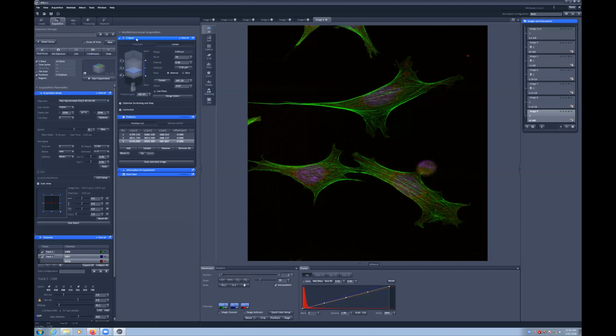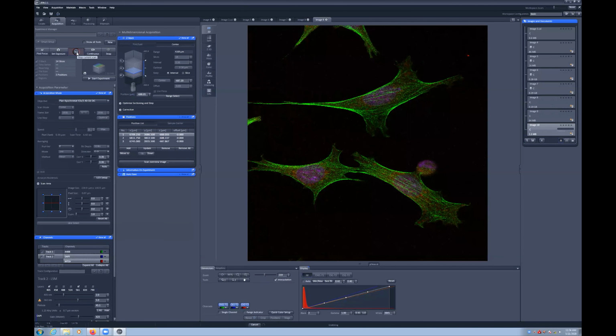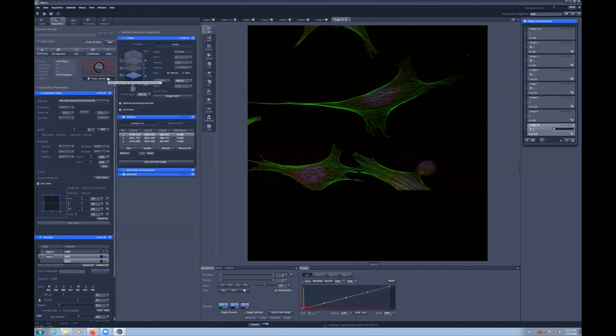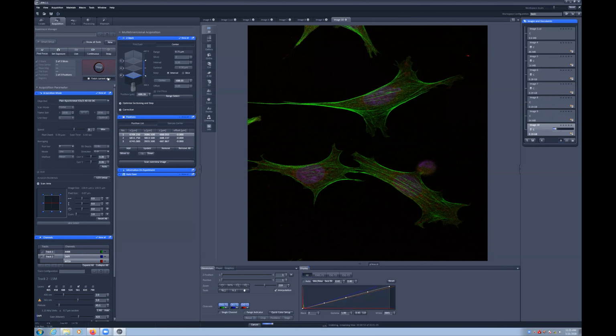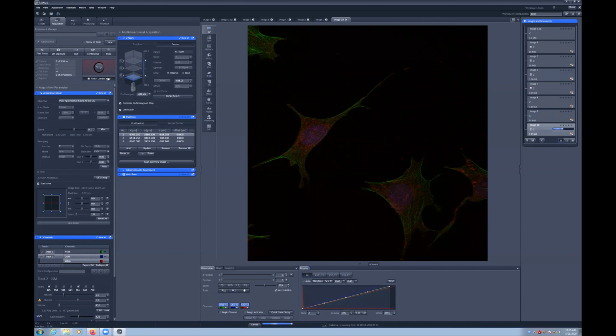You can also activate Z stacking and positions. Ensure that you are on center mode for any multi-point acquisition. Visit the first point and ensure that it is in focus as before and select the center button on the Z stack menu. When clicking Start Experiment, it will visit each point and capture a Z-stack. Note that here we are only capturing 3 Z-stacks as an example. These will be available as a separate slider in the Dimensions tab.